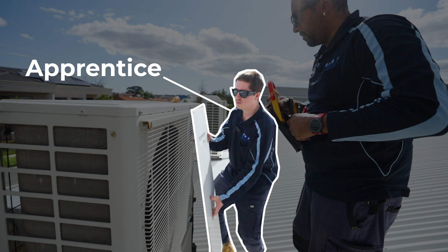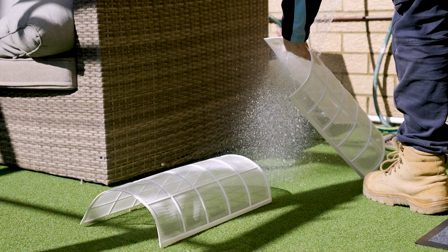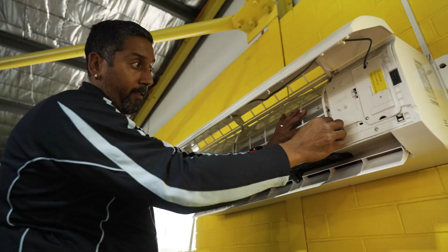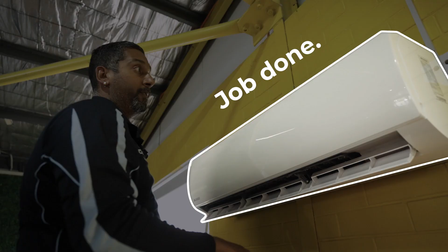So now that this closed, we can go back inside and we can turn it on, fire this unit up and see what it's doing. We've come back in and the fan seems to be running, so that's a good sign. So we've got airflow going through. In this case, it looks like it could have been the filter restricting it. Now we'll get the correct airflow through the unit, and by cleaning these filters out, we can now feel that the airflow is restored.